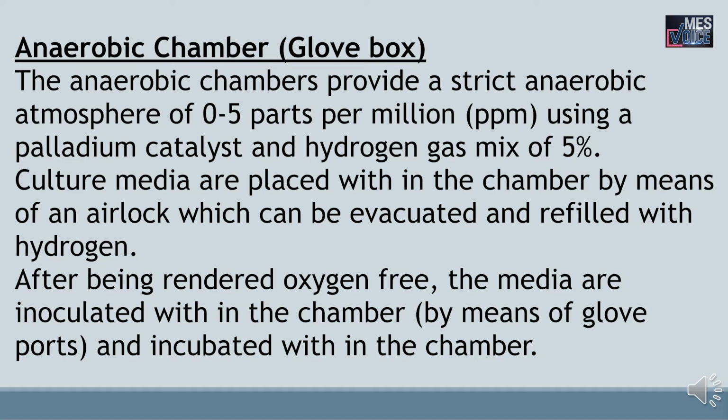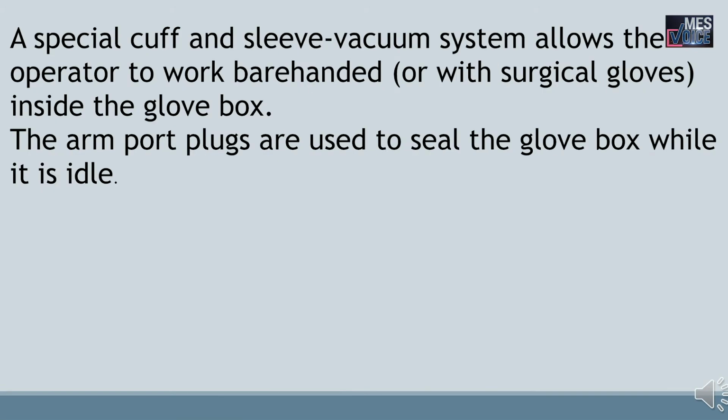Here culture media are placed within the chamber by means of an airlock, which can be evacuated and refilled with hydrogen. After being rendered oxygen free, the media are inoculated within the chamber by means of glove ports and incubated within the chamber. A special cuff and sleeve vacuum system allows the operator to work bare-handed. The glove ports also consist of surgical gloves. The arm port plugs are usually kept in place when they are not in use.